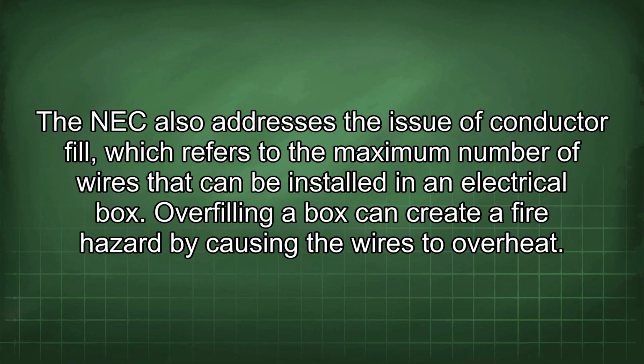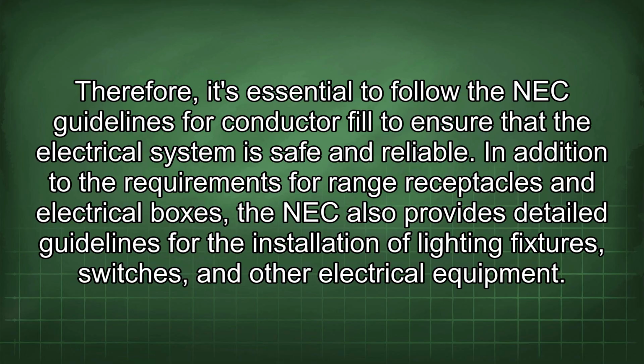The NEC also addresses the issue of conductor fill, which refers to the maximum number of wires that can be installed in an electrical box. Overfilling a box can create a fire hazard by causing the wires to overheat. Therefore, it's essential to follow the NEC guidelines for conductor fill to ensure that the electrical system is safe and reliable.